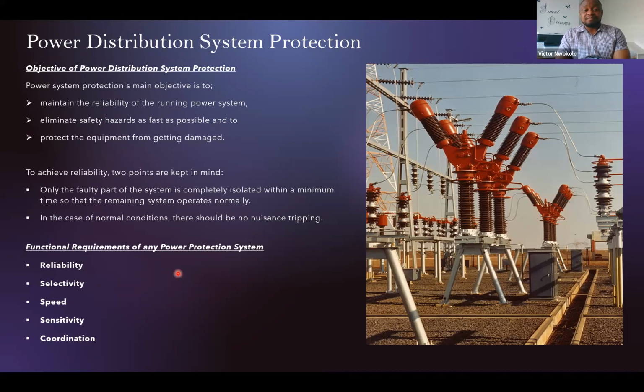And then there are some functional requirements for protection system. These are basically five requirements to consider when designing a protection system. One of them is reliability. The protection system must have the ability to operate correctly when called upon in the event of a fault in a power system. So one, it must be ready to operate, and two, it must operate correctly, and that gives you the reliability.